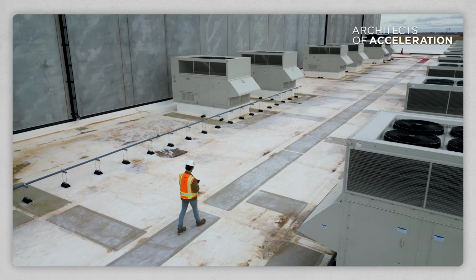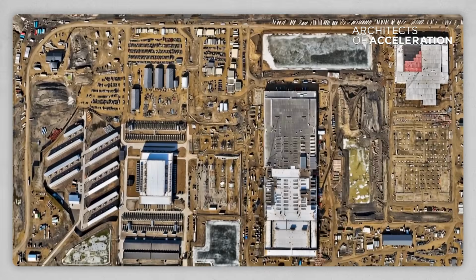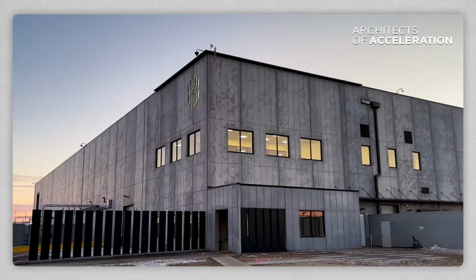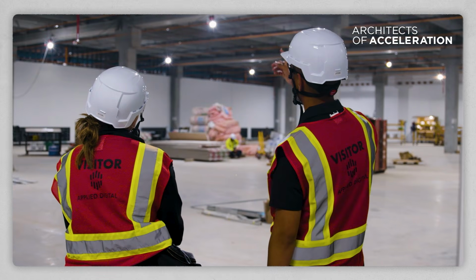And Laura, what are the biggest differences between commissioning a traditional data center and a high-density AI facility like Polaris Forge? The first major difference is scale. It's much larger to commission a 100 or 150 megawatt building than a 9 megawatt or even 20 megawatt data center. So you have a lot more equipment working together that you've got to test, make sure is running, and get operational.